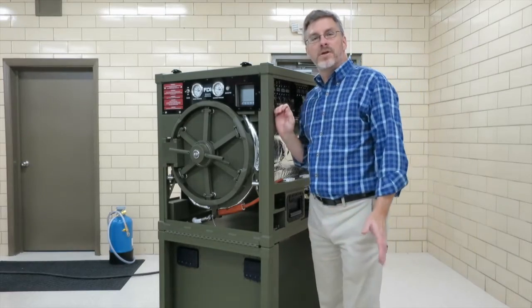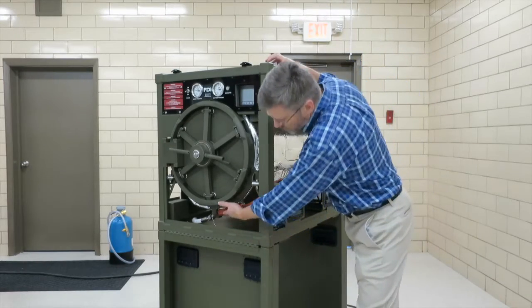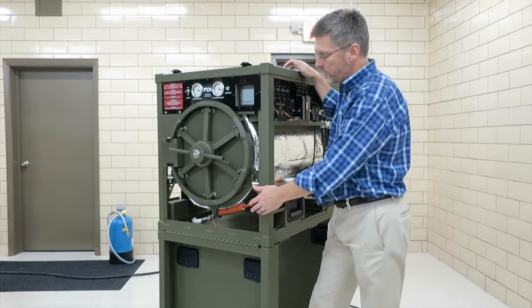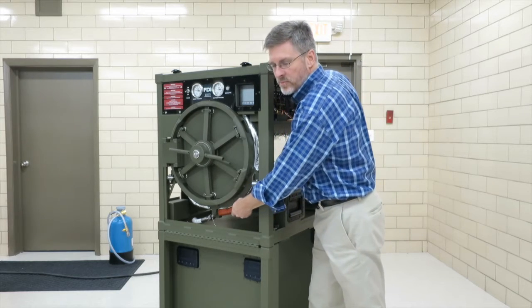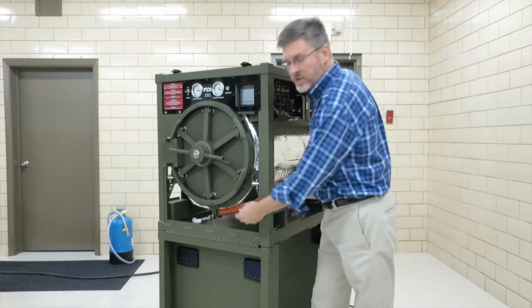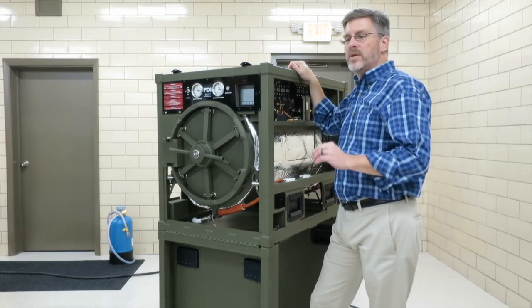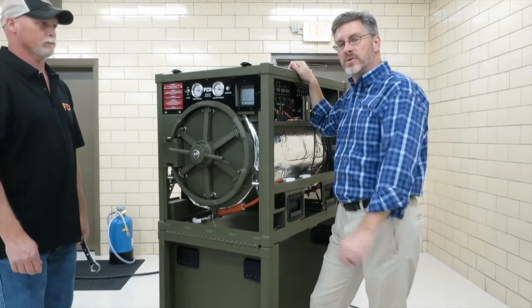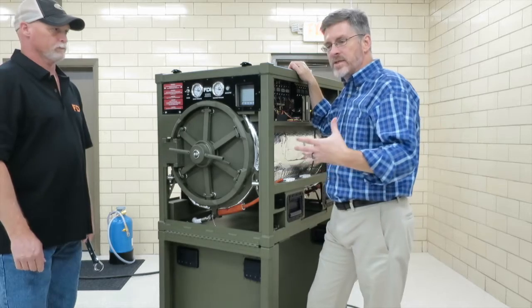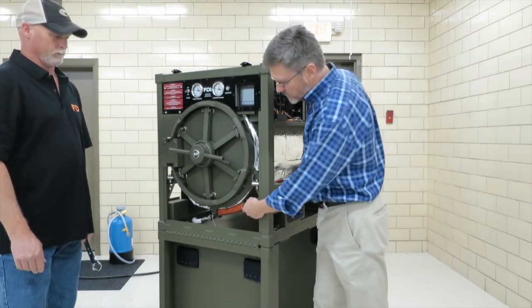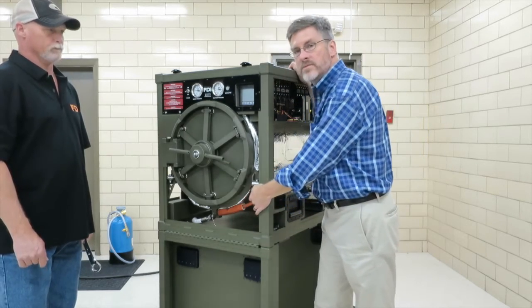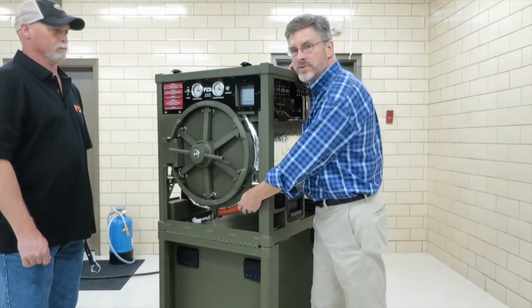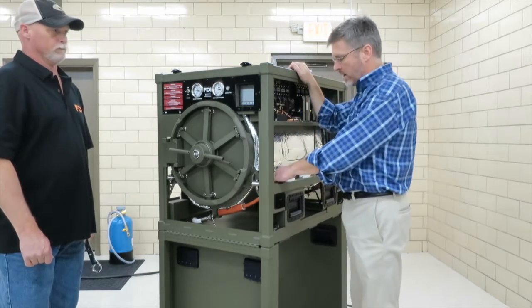All right, we've got the panels off. The probe is underneath this insulation sleeve. We're trying to keep the probe and all the tubing associated with the RTD probe as hot as possible during exposure, just to keep that very, very uniform. So this orange sleeve is actually silicone on top of fiberglass, so it's providing insulation all the way up to here.